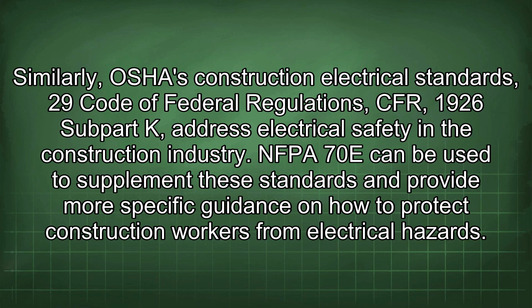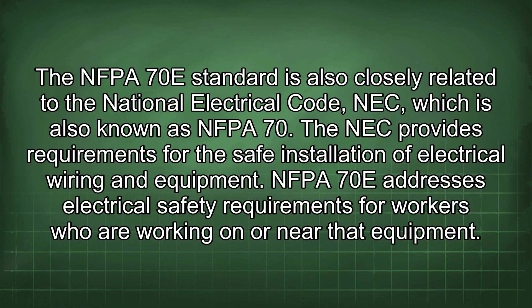The NFPA 70E standard is also closely related to the National Electrical Code, NEC, which is also known as NFPA 70. The NEC provides requirements for the safe installation of electrical wiring and equipment. NFPA 70E addresses electrical safety requirements for workers who are working on or near that equipment. While the NEC focuses on safe installation, NFPA 70E focuses on safe work practices. The two standards are designed to work together to ensure that electrical systems are both safely installed and safely maintained.